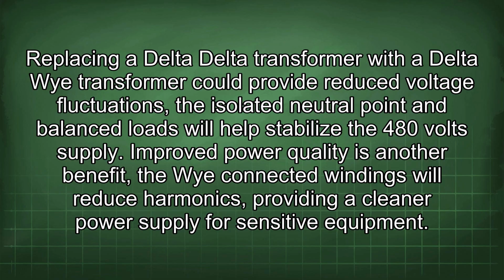Replacing a Delta-Delta transformer with a Delta Wye transformer could provide reduced voltage fluctuations. The isolated neutral point and balanced loads will help stabilize the 480-volt supply. Improved power quality is another benefit. The Y-connected windings will reduce harmonics, providing a cleaner power supply for sensitive equipment.